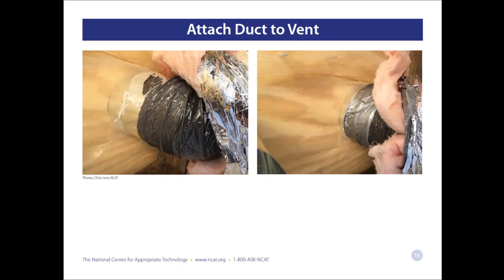A note about how to install the flex duct. This is insulated flex duct that's run to the vent hoods. And the reason it's insulated running to the vent hoods is you're drawing in cold air from the outside, and you don't want condensation to form on the cold air intake. And the other reason is the warm air is being taken to the outside, and you don't want to lose the heat from that warm air to the outside. So these need to be insulated.